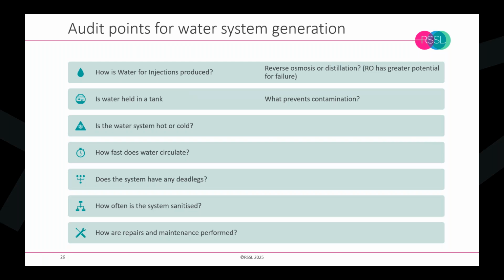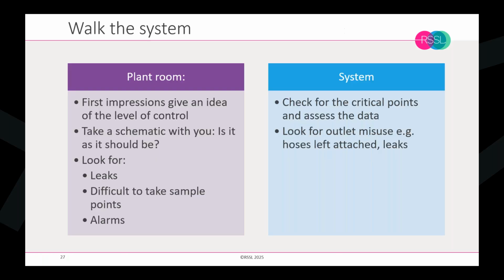And where we have hot water systems, then it's also understanding what temperature that water is at, and is that sufficiently high to be self-sanitizing? Generally, it's around the 65 to 70 degree mark, that Celsius, that we can achieve that level of control through heat. And we also need to go around checking for dead legs, and we'll look at some examples in a moment, and also how repairs and maintenance are undertaken. But with any audit of a water system, walking the system is really important. You can't do it as a desktop exercise.